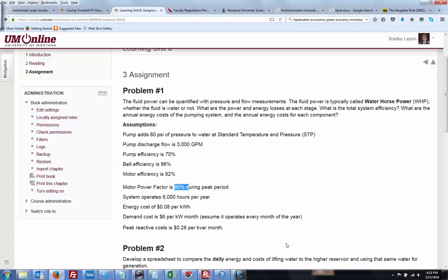and really it's going to charge you 28 cents every time. It's not going to keep charging you every single day, but if you hit whatever maximum kVAR you hit is what it's going to charge you. So that 28 cents is kind of factored into it. It might be like 1 cent per kVAR per day, but if you're running for 30 days, or 28 days, that's basically the whole month's charge. It's a little bit weird. But so let's multiply that by 28 cents per kVAR month, I think.